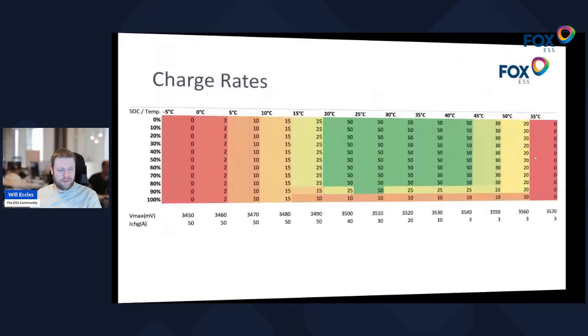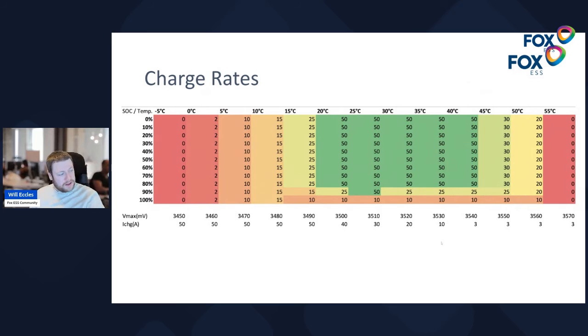An easier diagram to look at is this one, again kindly provided by Fox, that shows the optimum position being around 25 degrees Celsius. At 25 degrees Celsius, the chemistry is performing the best. You can see this is amps, so 50 amps, which is most inverters' maximum output, all the way up to 90% state of charge, where it then starts to limit. That's because the battery is nearly full, so it starts to ramp down the charging current so as not to overshoot and damage the battery. At 25, you can go up to 45 Celsius before you really notice any impact, which is great. And you can see as we go down, the amps reducing.